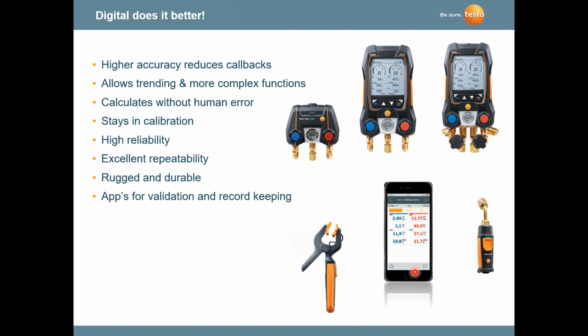It's higher accuracy reduces callbacks. It's all about the accuracy of the sensors that we're using for the pressures, all about the accuracy of the temperature pipe clamp probes that I went through with the NTC probes. There's other things that it does. Obviously, it allows trending. You're charging a system while you're looking at the changes in the pressures, the temperatures, the superheat, subcooling. There's no human error because it's all done automatically for you. It does stay in calibration. I can go through that a little bit later.